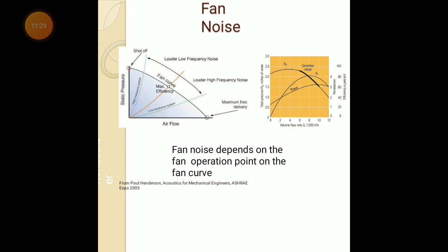Estimating fan noise: let's say LW is the fan sound power level, KW is the fan specific value, Q is volume flow rate in CFM, P is static pressure in terms of inches of water, BFI is blade frequency increment. So the formula is given as LW = KW + 10 log10 Q + 20 log10 P + BFI + C.